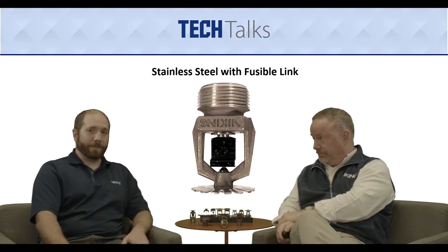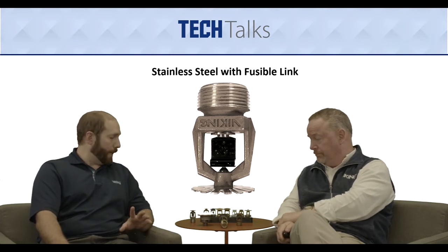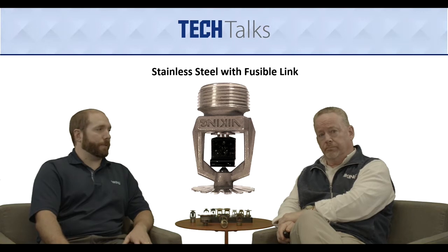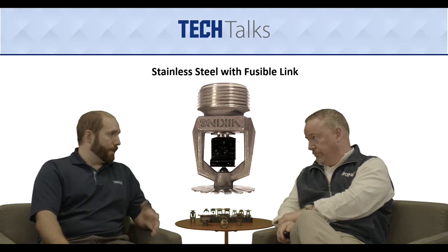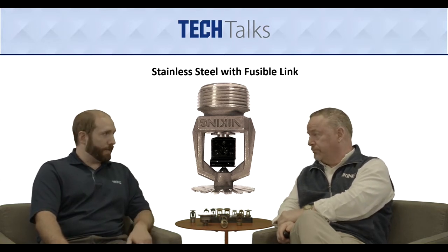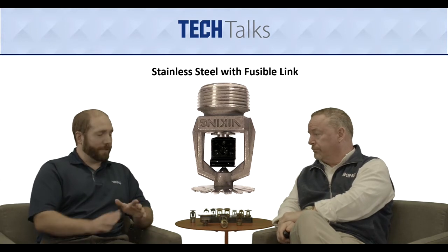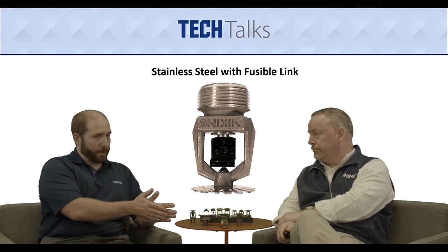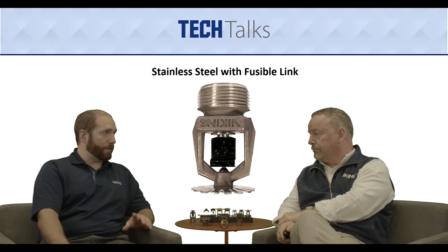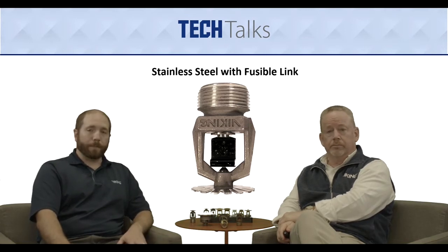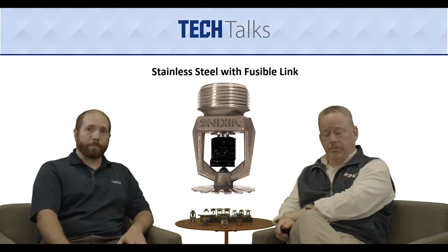So yeah, stainless steel, fusible link. This sprinkler happens to be the VK368 specifically. We offer 8K and 5.6K stainless steel sprinklers. The 5.6K line is glass bulbs. The 8K VK368 is the link. Okay. Cool. That's great.